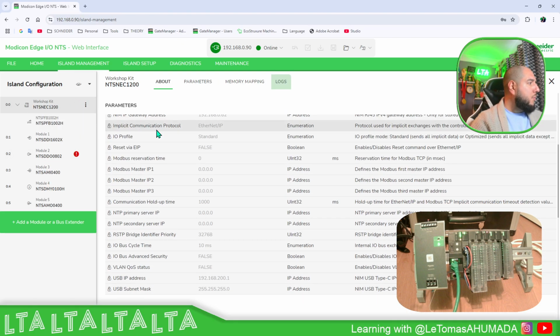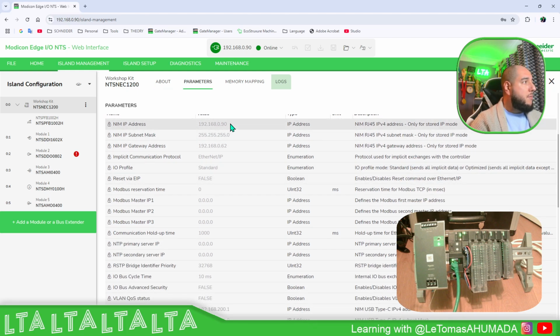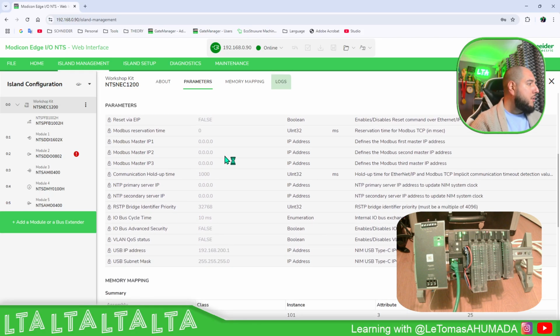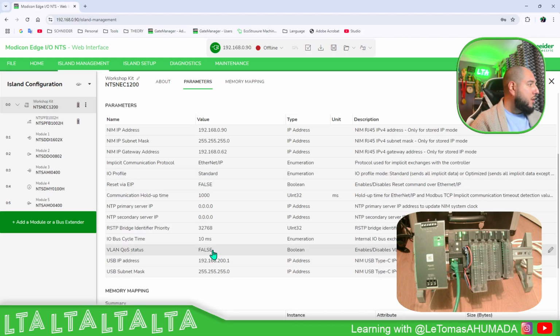Okay, so what I'm going to do is change a few things here. I'm going to use Modbus TCP in order to connect with the Modicon M580 NOC card. So this IP address is going to be just fine for me. What I need to change is this part, the return IP to Modbus TCP. And then if you are going to use it on the RIO network, just need to enable this part. So what I'm going to do is be offline. I'm going to disable this part for the moment. I'm going to go only to the NOC. So here I'm going to use Modbus TCP.